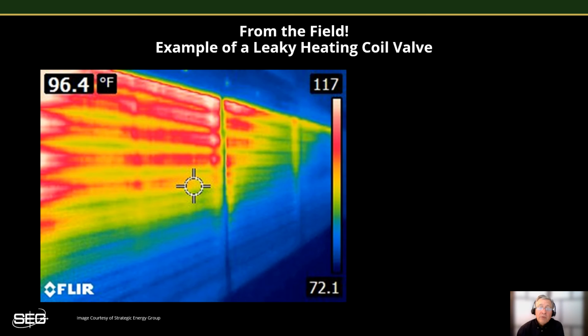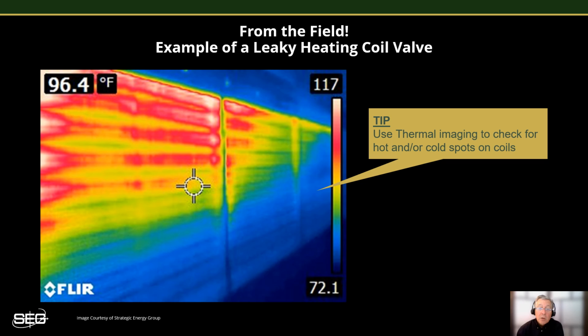But by viewing it with infrared, you can easily see that heat is definitely leaking by. Note the white and the red and the yellow areas where the coil is the warmest and how the heat from the hot water that's leaking by the valve dissipates, turning green and then blue as it moves across the coil, and the heat is carried away by the airstream passing through the coil. Thermal imaging is a great tool for quickly identifying leaky heating and cooling coil valves.